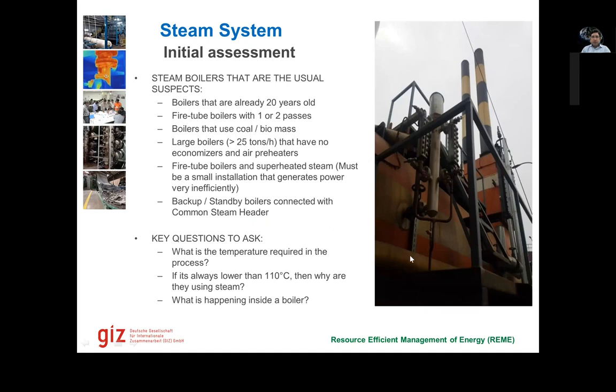Usually a big utility that we have in the textile sector is the steam system. And usually when we go to the steam boilers, we do an initial assessment. So boilers that are old boilers, for example 15-20 years old, or fire tube boilers which have only one or two passes, then boilers that are using coal or biomass, these are usually the ones that have a lot of inefficiency issues.